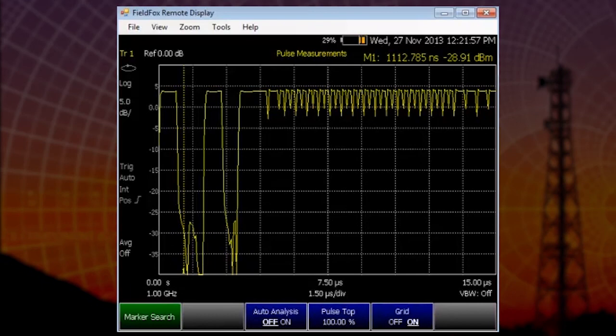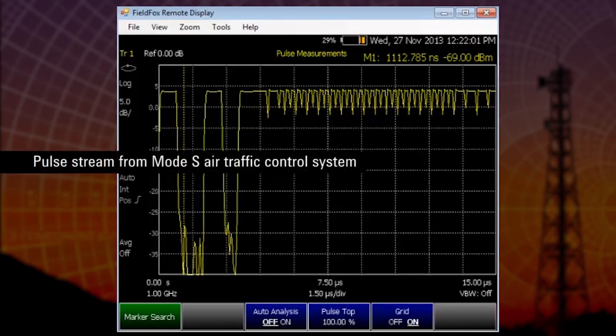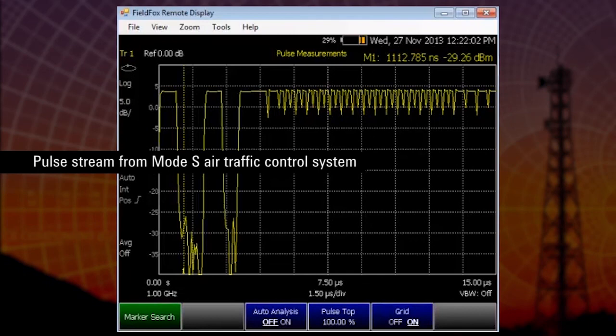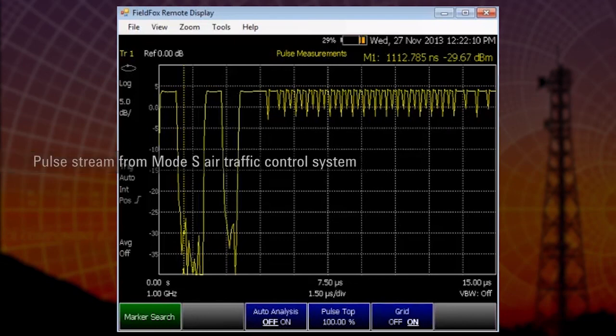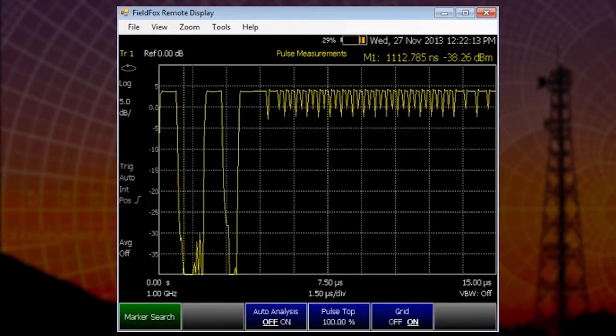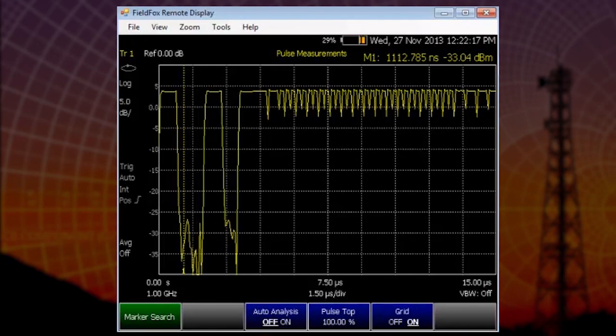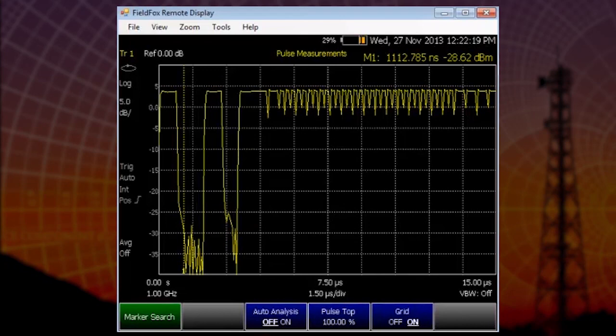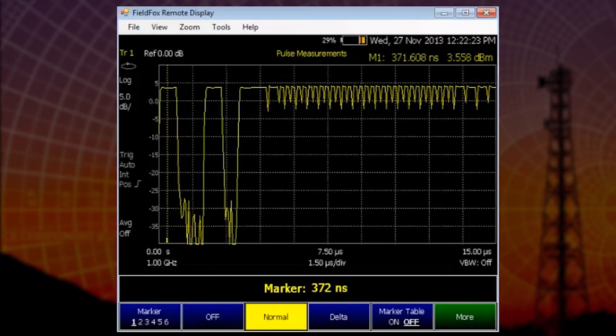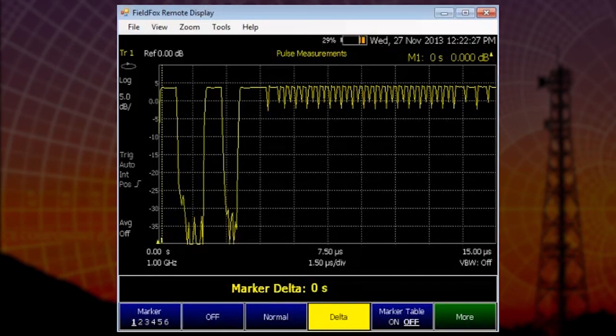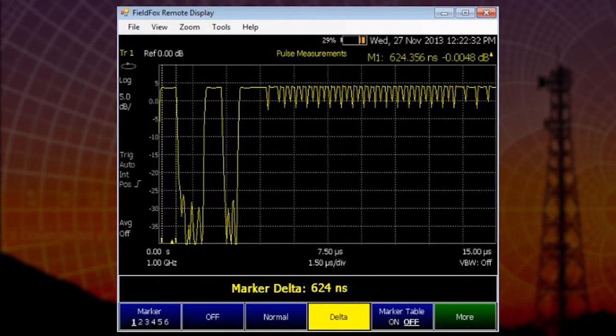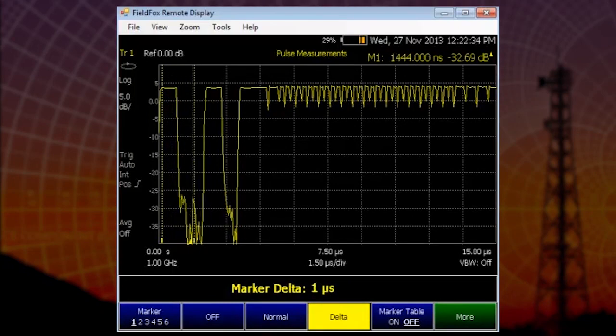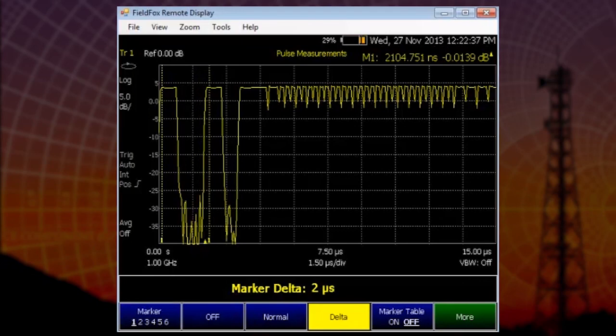Now I've set up my signal generator to output a pulse stream from a Mode S air traffic control system. These systems are used worldwide by almost every international airport. What we're able to see here is the pulse strings from the MODES interrogator and then also the signaling. Let's measure the pulse width using our markers. This is a very simple process. We can measure the pulse repetition interval.